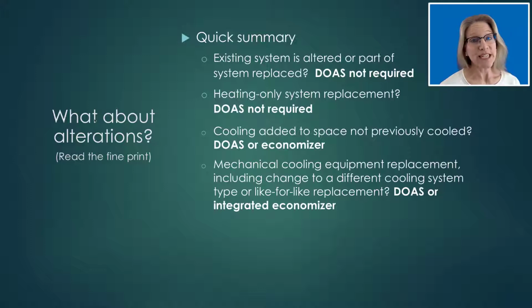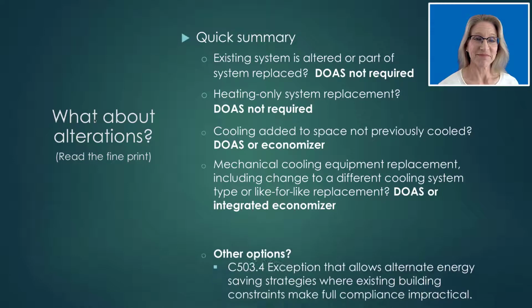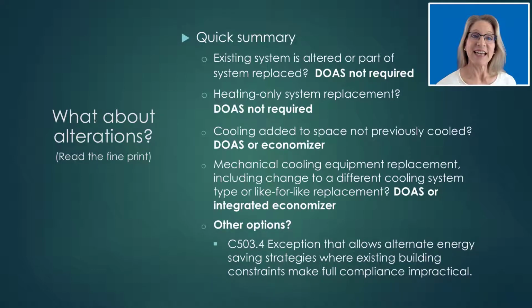If mechanical cooling equipment is being replaced, and this would include either switching to a different cooling system type, or if it's just a like for like, then you can either show compliance via the DOAS provision or via integrated economizer. And then there is an exception that allows alternate energy saving strategies in those scenarios where there are constraints within the existing building that would make compliance with either the DOAS or the economizer provision impractical.